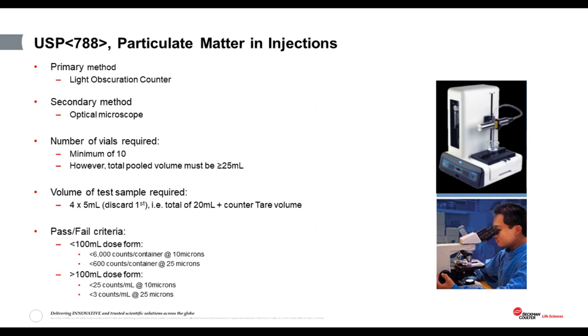And for example, when vials of the final dose form may only be 1 milliliter, which is quite common, the user would have to combine not just 10, but a total of 25 vials to achieve the required 25 milliliter pooled volume. Now, results from the first of the 4 samples are discarded, and this is to try to reduce test-to-test carryover. And for small volume injectables with a dose form of less than 100 milliliters, the maximum particle counts per container is the pass-fail criteria, so it's per container.